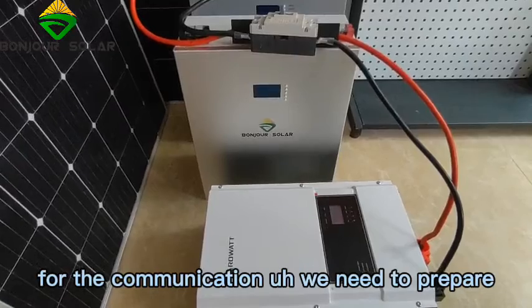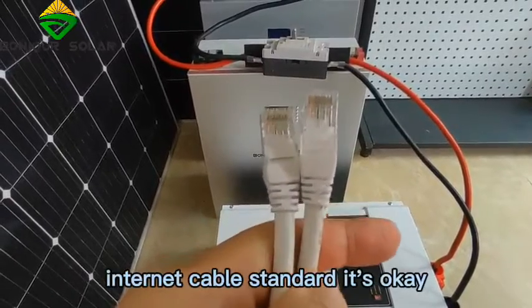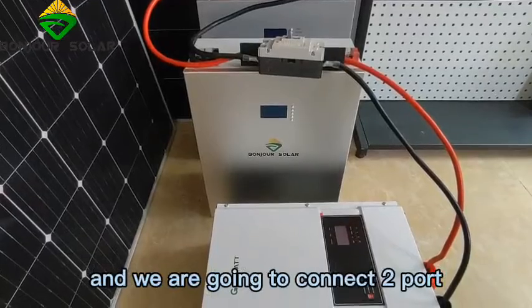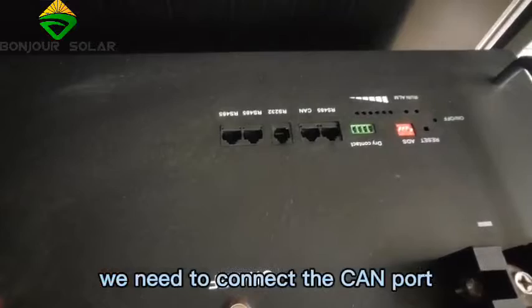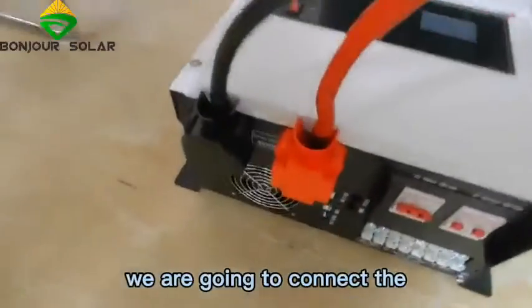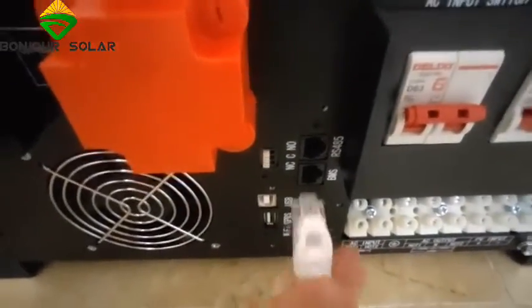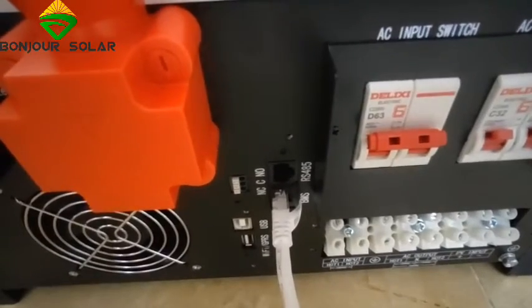For the communication, we need to prepare a standard internet (Ethernet) cable. We are going to connect two ports. From the lithium battery, we connect to the CAN port — remember it is CAN, not RS-485. Then for the Growatt inverter, we connect to the BMS port. The communication cable connection is complete.